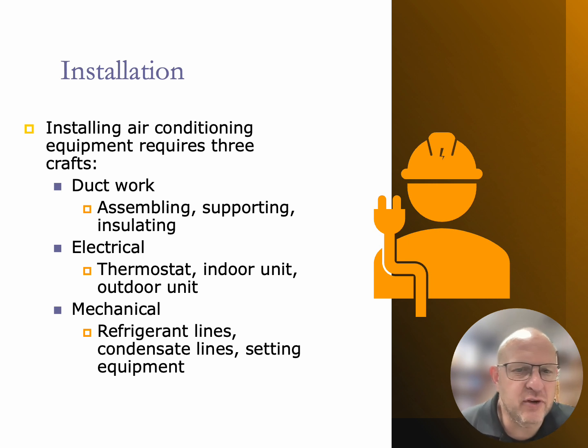Now, the installation of an air conditioning system actually requires the individual to know three different trades. Not only the heating, ventilation, and air conditioning trade, but the electrical trade, and then to be mechanically minded as well for installation of that system. So installing an air conditioner will require you to understand ductwork, assembling that ductwork together, measuring that ductwork to make sure you're getting the proper airflow and static pressure within that system, total pressure and velocity pressure off of that duct. You will also have to understand the supporting aspect of it as you're running different types of duct board, flex duct, metal duct within that system.